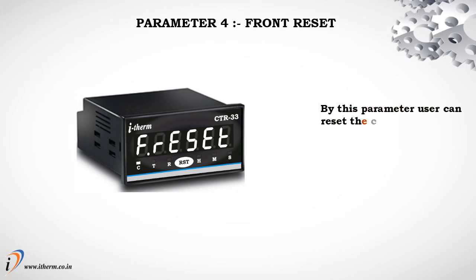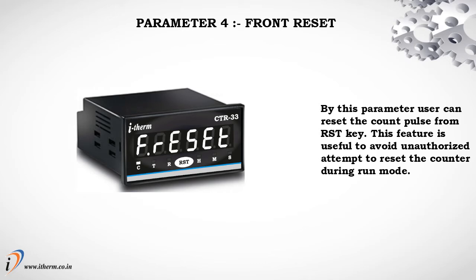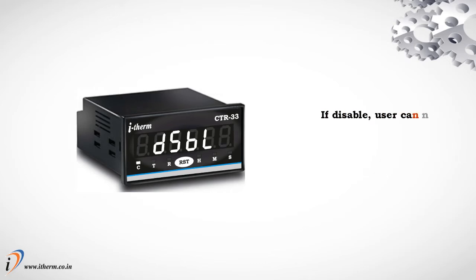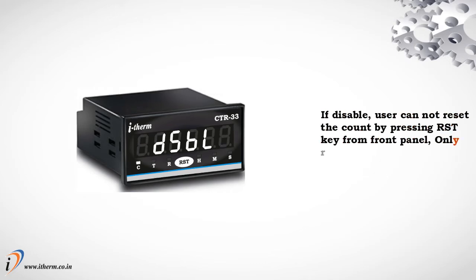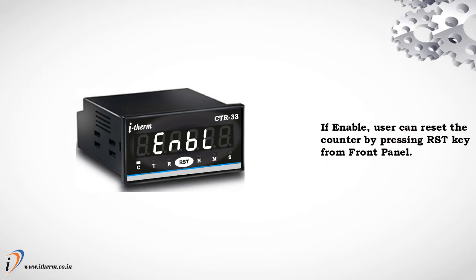Parameter 4: Front Reset. By this parameter, the user can reset the count pulse from the reset key. This feature is useful to avoid unauthorized attempts to reset the counter during run mode. If disabled, the user cannot reset the count by pressing the reset key from the front panel; only remote reset from the back terminal is allowed. If enabled, the user can reset the counter by pressing the reset key from the front panel.